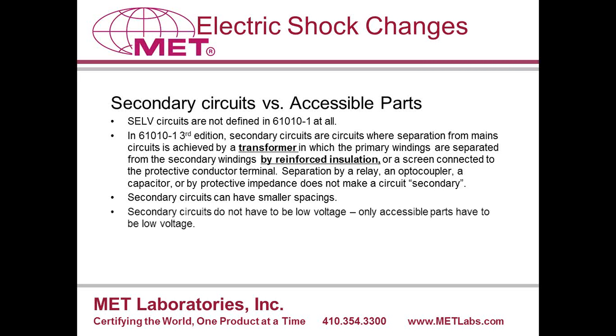In contrast, an accessible part does not have to be separated from mains by reinforced insulation, such as a transformer. It can be separated by another component or protective impedance or some form of basic insulation, but it has to be either low voltage or low current, low capacitance. Second edition did not define secondary circuits, although they were frequently referenced. So this change is just a clarification. It does not affect any tests or any other requirements in the standard.